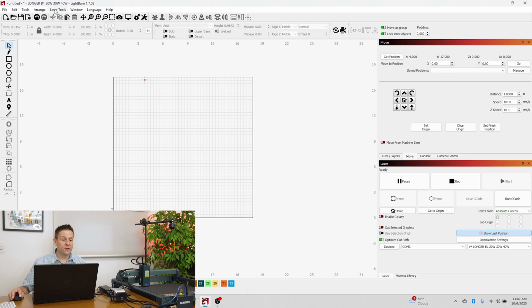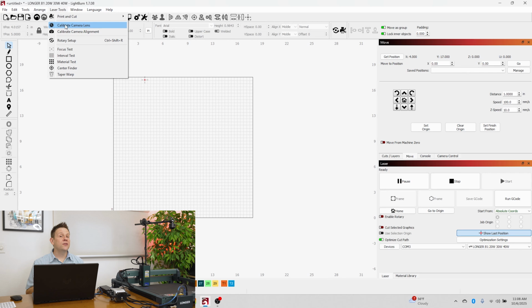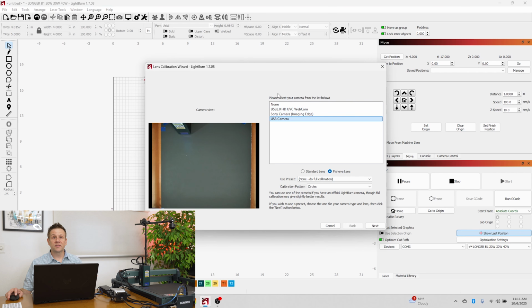From here, I'll navigate to Laser Tools and Calibrate Camera Lens. This is going to start a two-step process, starting out with presenting the target pattern up to the camera. Pretty straightforward process. From there, it's going to immediately take us into Calibrate Camera Alignment. This is where it's going to engrave a test pattern on that poster board, and then we're going to associate where the camera picks up that pattern to where it is on the computer screen, and that will complete the setup process.